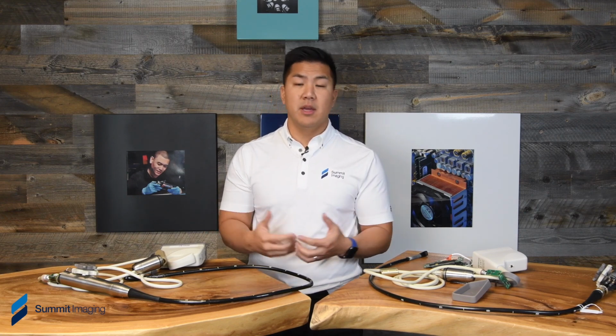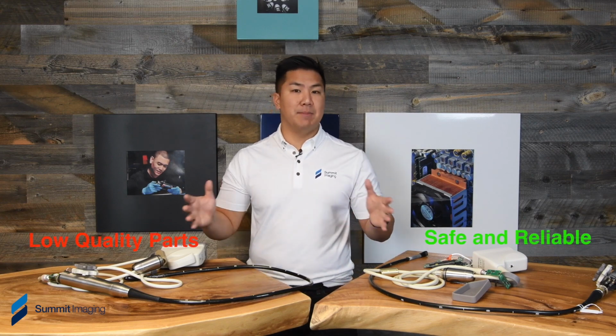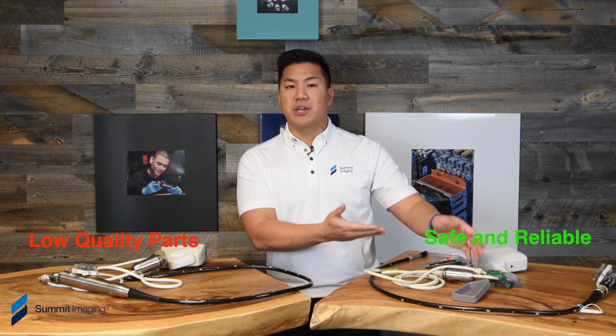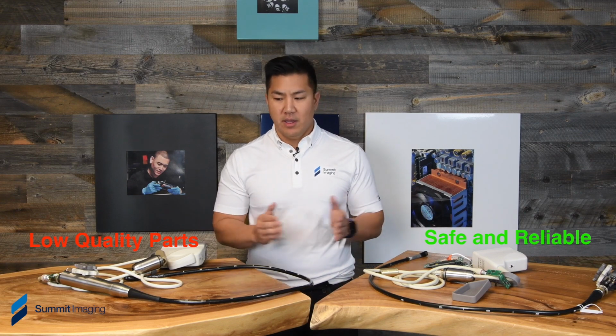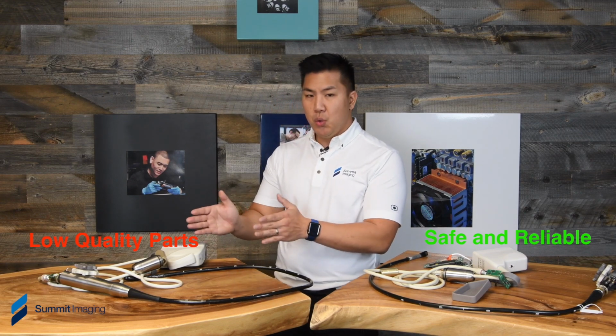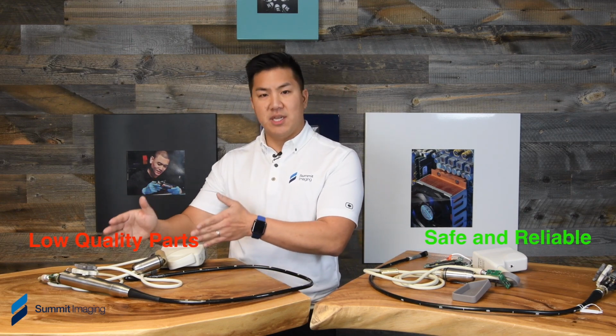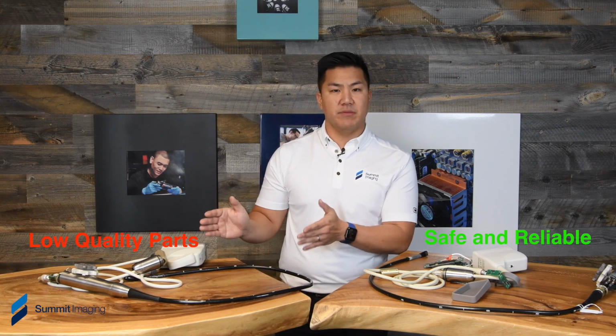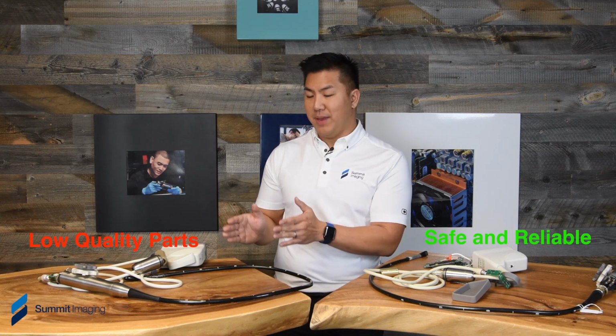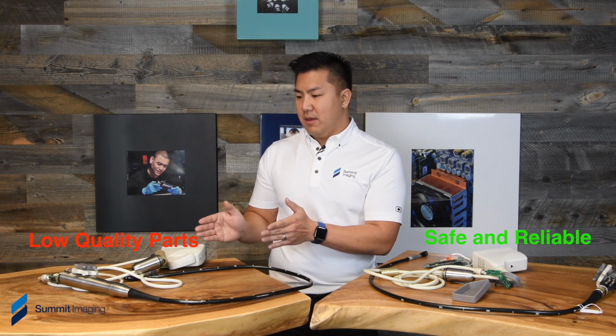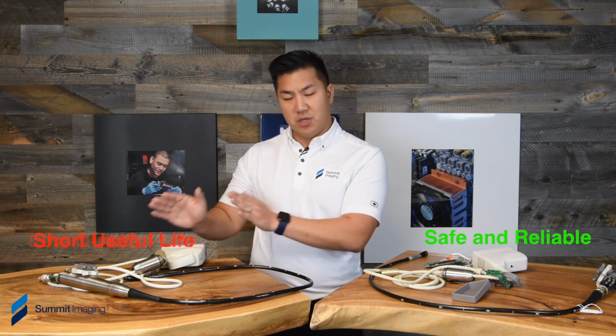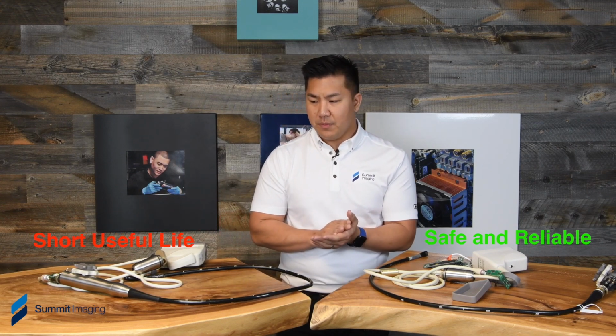And in addition to that flexibility, which gives you longevity, reliability, and extends the mean time between failure, it also has a correct strain relief to do the exact same thing. And so what we're seeing is two low quality parts installed on a high value piece of equipment that's critical for patient scans, actually going to decrease the useful life of this piece of equipment.